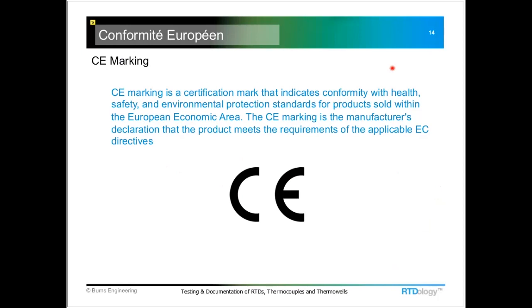And CE marking, in some cases we've seen where a CE marked temperature probe is necessary. Most of the time, however, the temperature probe is part of a larger system. It may be attached to a transmitter, or it may be installed inside of a larger system that carries the CE marking, and so the individual components don't actually need to have that. But in some situations, the actual temperature probe will be marked with CE, and it's purely a European-driven requirement, and it just says that it's been tested or evaluated against some directives that are out there. One that comes to mind is with electrical items, that it's not going to give anybody a shock, or the level of energy in it is low enough so that can't happen. And there's also, I think, a pressure directive. Those would be the two most common ones.